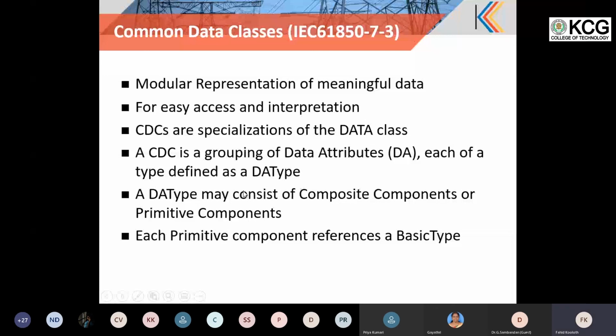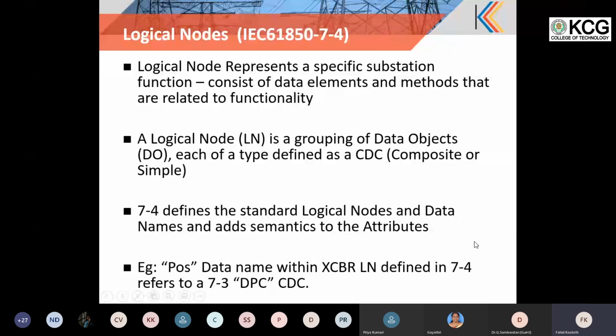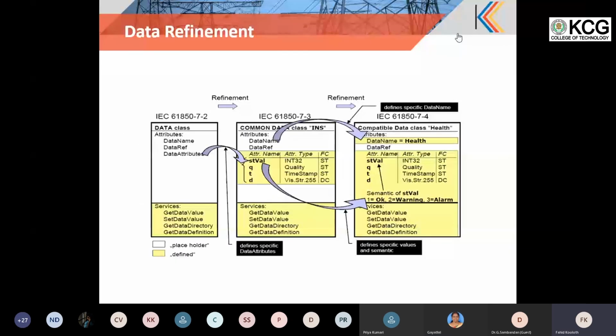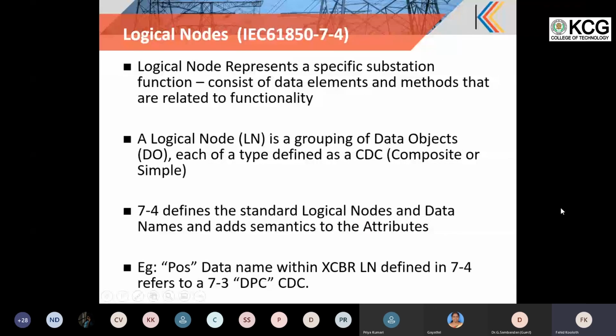Yes, sir. Yeah. So moving on to the logical nodes. This is nothing but a functional representation of the data given in the logical node. As I mentioned, all the substation classified functions are represented as logical nodes. So circuit breaker can be a logical node. Protection, all the protection functions can be a logical node. All the measurement can be a logical node. And this is defined under 7-4, and 7-4 further mentions the CDCs under it, and the common data classes are specified under 7-3, which is linked with 7-4.